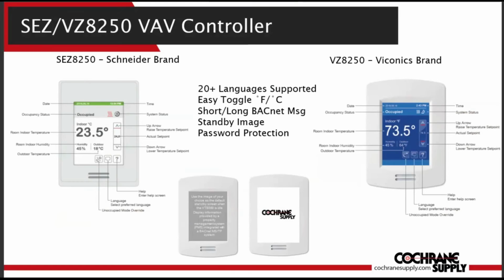Long BACnet messages take over the entire screen. It's typically used for messages letting the occupant know of an event happening in the facility, like a meet and greet happy hour at a hospitality installation, to a warning, as in a shelter in place message for educational or commercial installations.